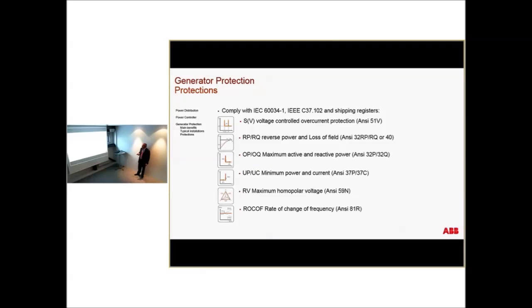And this is the parameter that can protect. Basically, these parameters are defined by the ANSI standard for generator protection: voltage control over current, reverse power loss, maximum active and reactive power, minimum power and current, maximum voltage, and the ROCOF, the rate of change of frequency. This is very important because this is normally embedded in a professional generator protection. So basically, this is an additional feature that we have inside the release.